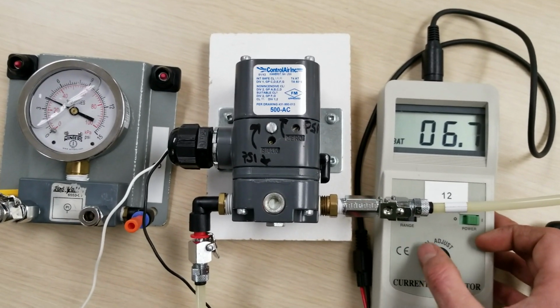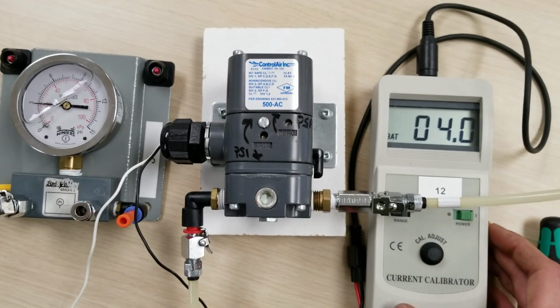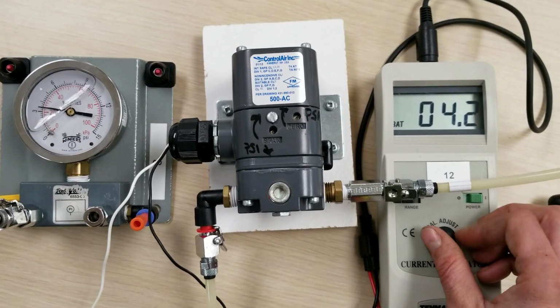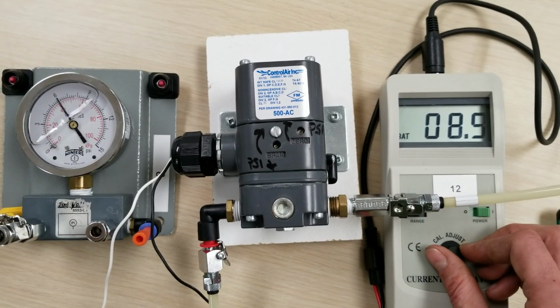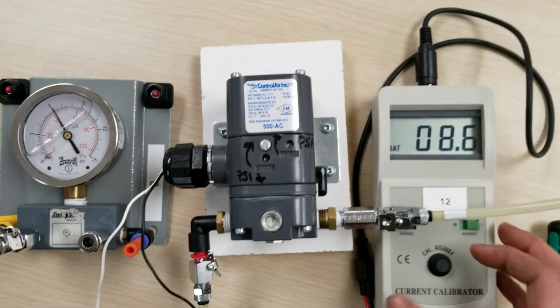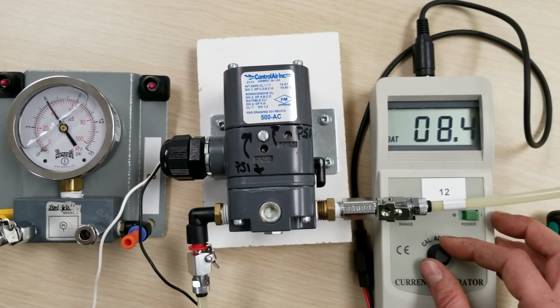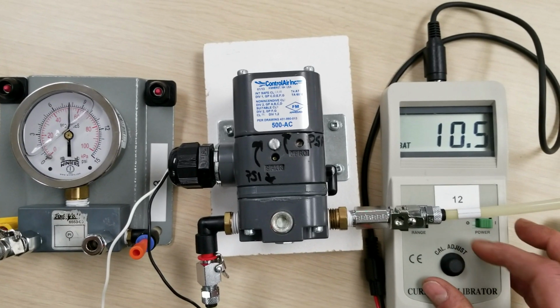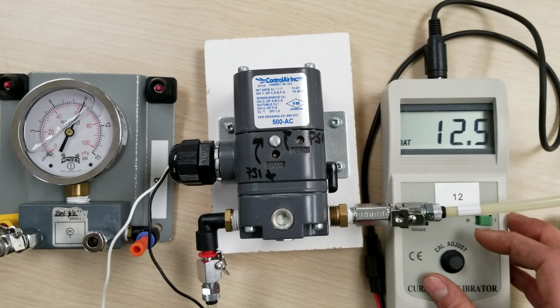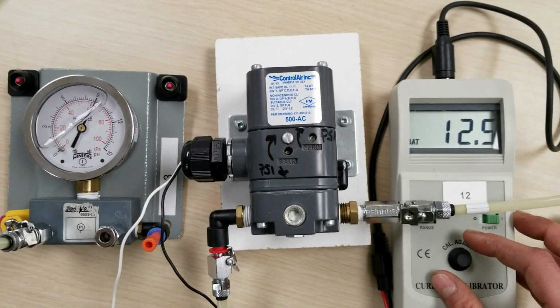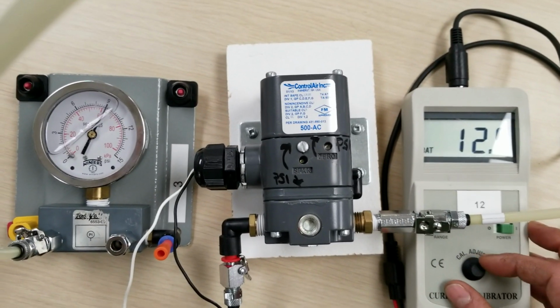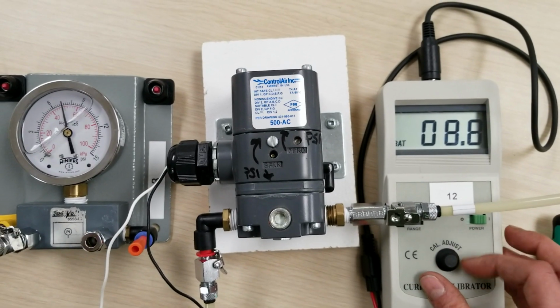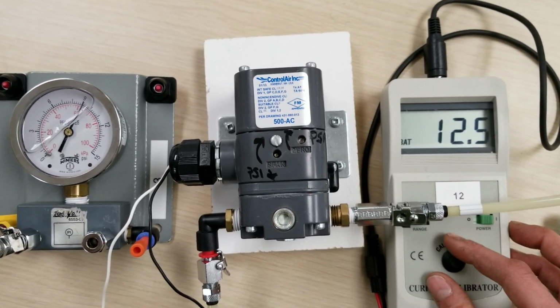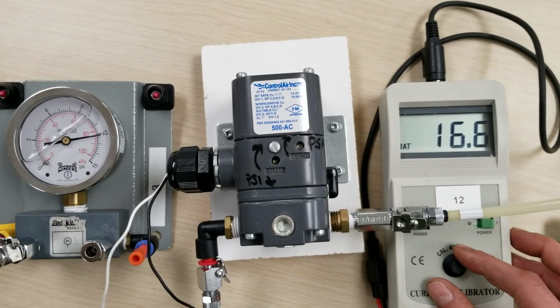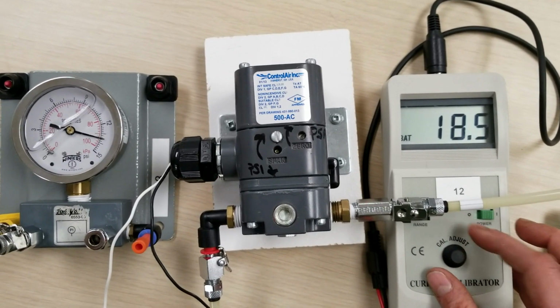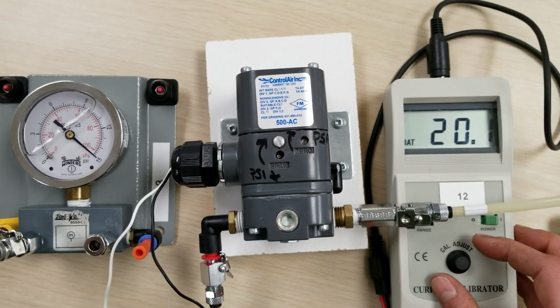So if we were to draw a graph, we would be starting at 3 psi and 4 milliamps. We would want 6 psi at about 8 milliamps. Oops. 9 psi, I apologize, 9 psi at 12 milliamps, and that should have been 6 psi at 8 milliamps, 9 psi at 12 milliamps, 12 psi at 16 milliamps, and 15 psi at 20 milliamps.